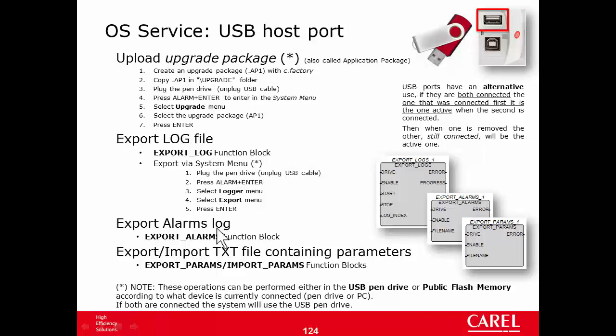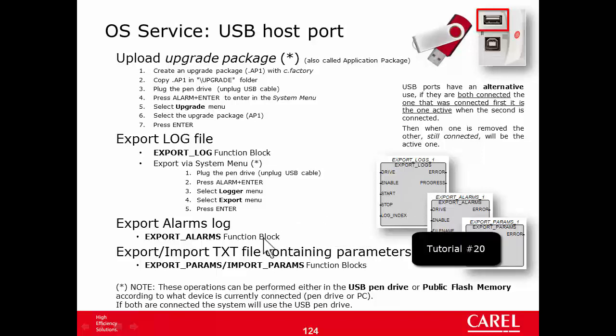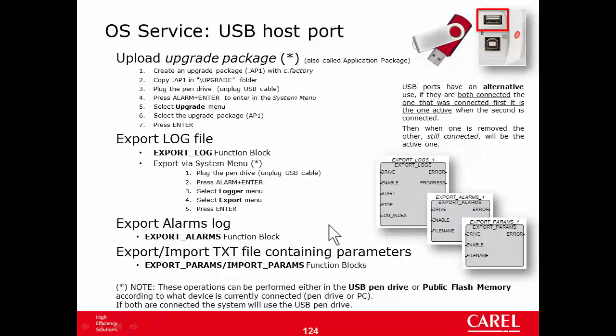You can export alarm logs using the export alarm function, similar to log export. You can also import and export parameters using the import-export-params blocks, as seen in tutorial 20. These operations — exporting logs and uploading upgrade packages — can be performed using either USB or the public flash memory depending on what is connected. If a pendrive is connected when the function runs, it exports there; otherwise, the system exports to the public flash memory.